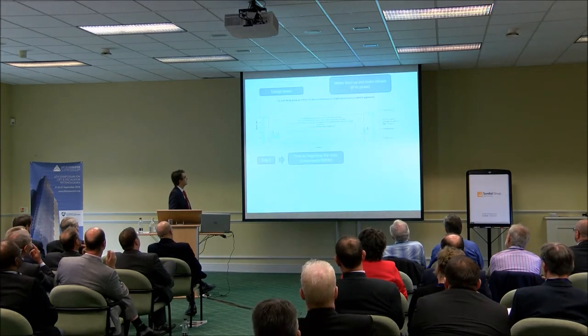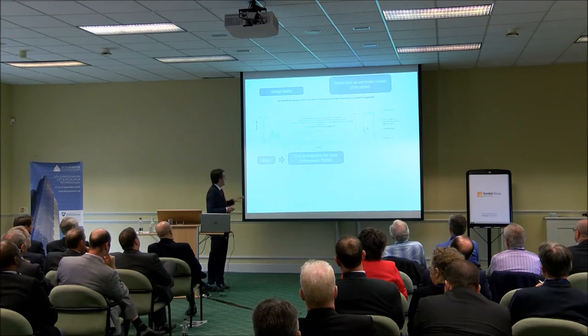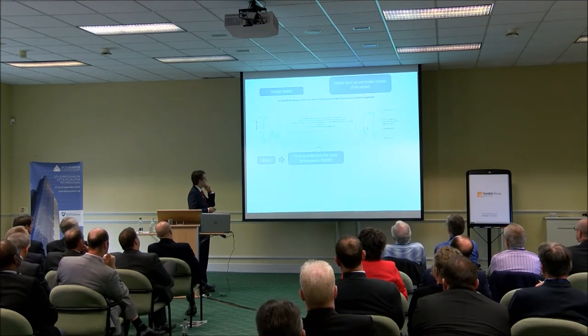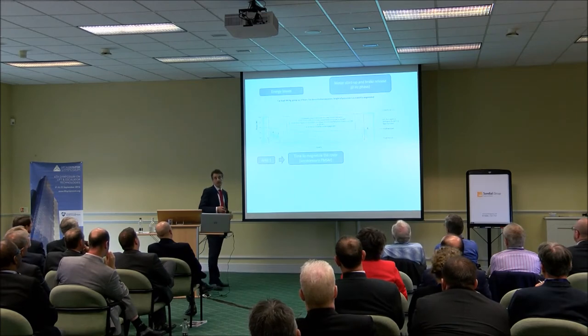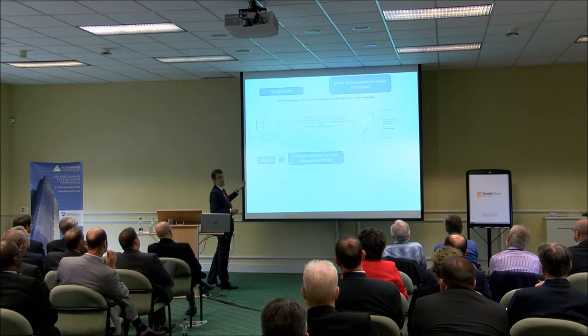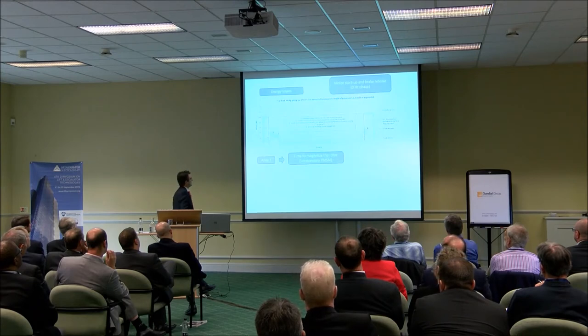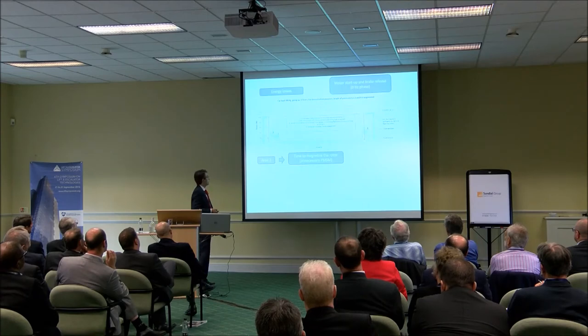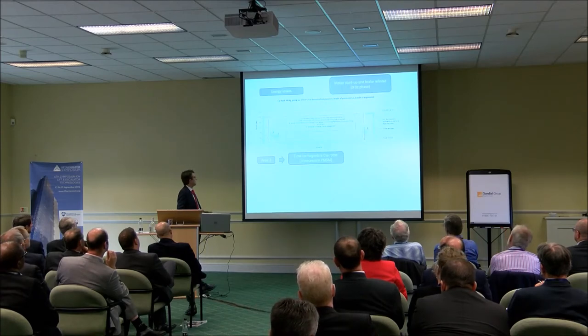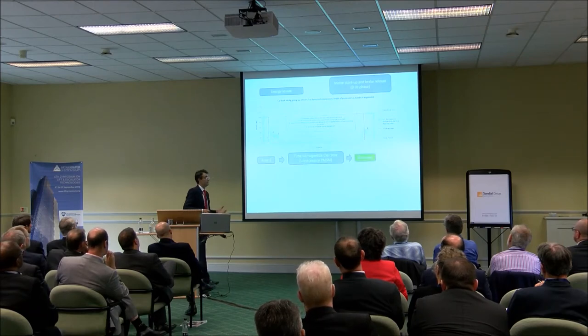This is the first phase: the zero hertz phase — motor start-up and brake release. We have a real graph from our test tower. On purple we can see the speed profile of the journey; on the vertical axis we have power, horizontal axis time. In blue we can see the power the frequency inverter and motor were demanding from the grid. In area number one there is an energetic demand — basically the frequency inverter is trying to magnetize the rotor. But in synchronous motors today, inverters don't need to do this operation, so we suggest to eliminate it.